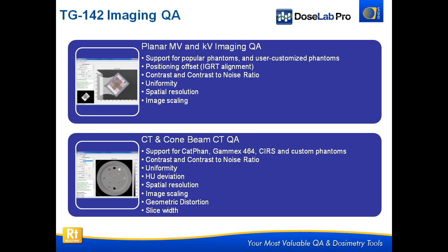We do CT and Conebeam CT QA. We support Catphan, Gammex 464, CIRS, and custom phantoms — if your phantom isn't on the list, you can manually add it. We calculate contrast and CNR, uniformity, HU deviation, spatial resolution, image scaling, geometric distortion, and slice width. All of this is fully automatic: you just point to the directory that has your DICOM files of your CT scan, click OK, and everything else happens behind the scenes.